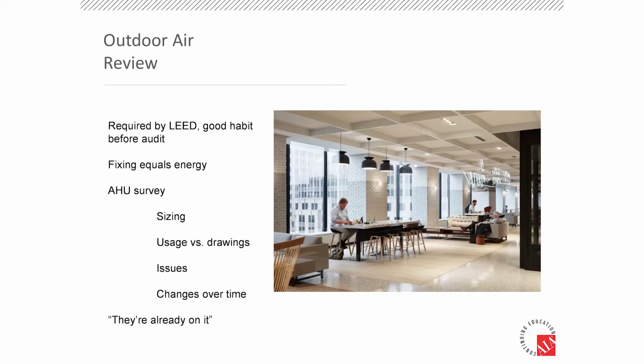So we took a couple of steps, because it's a building with, in the end, 35 large air handling units we had to go through and take readings on to verify ventilation rates. First, we created a schedule of the units, looked at the dampers, and looked at what they should be bringing in for outside air. Then we surveyed the building, visited the air handling units, and compared what's there to the original drawings and mechanical schedules, since those were the latest documents we had.